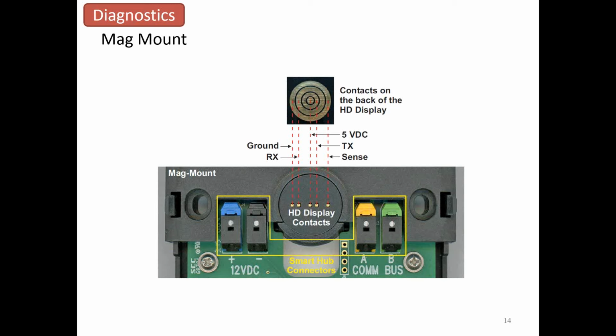Also, on the center of the back of your display, there's a pretty good little symbol kind of showing you what's going on. You've got communication, and you've got 5 volts DC going through this system. So ground to 5 volts, which is the outside ring and the center ring, you should have 5 volts DC on that display. And it shows you where they go on the hub itself, the mag mount that's on the wall. So you can actually take a meter and test it right there. And then the back side of your display snaps right to that and sends power there.